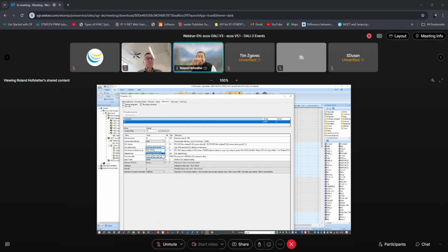In our case of the push button, we choose device address and instance address, and then it uses here the instance 0 as the push up button, and I take the information as a button information. The binary input can only be on or off, so push button pressed or released.